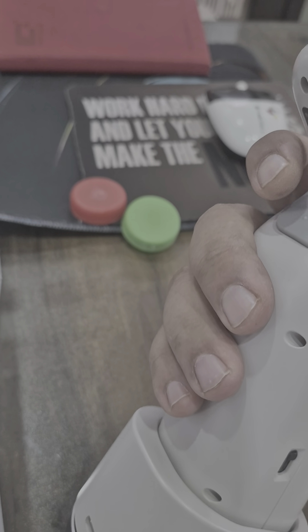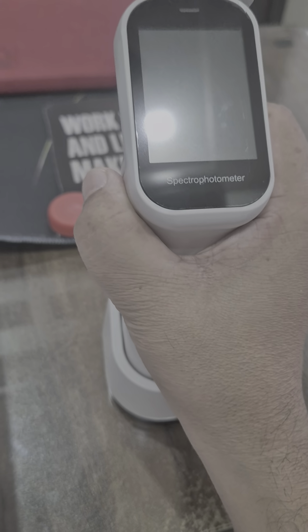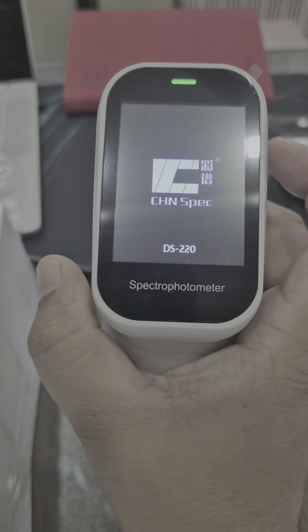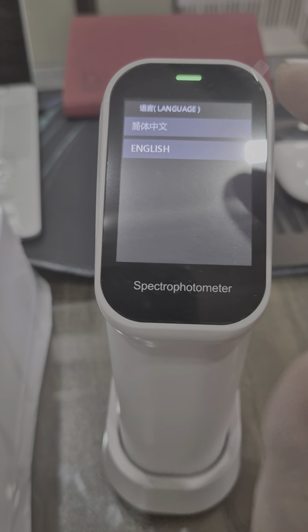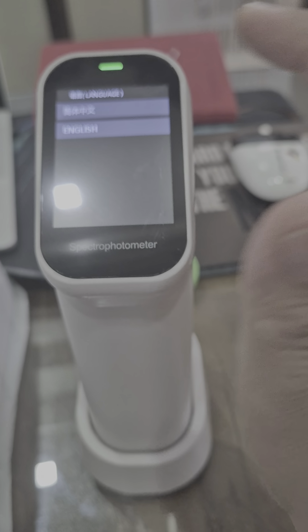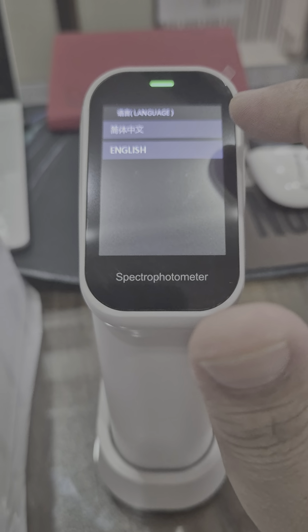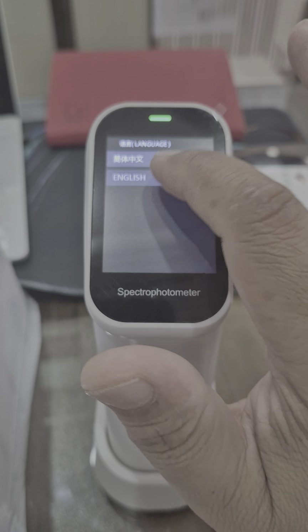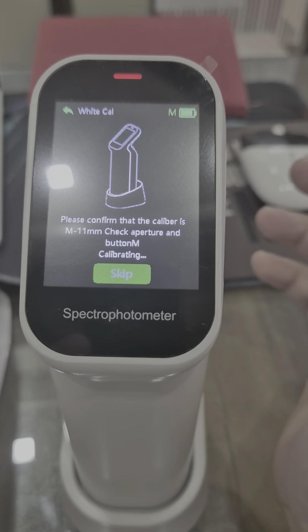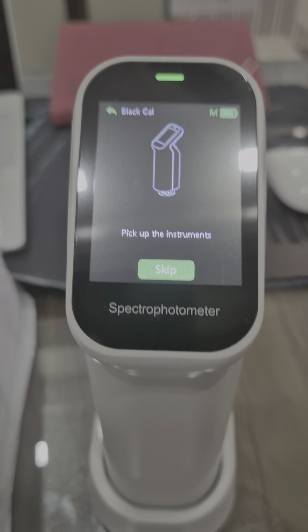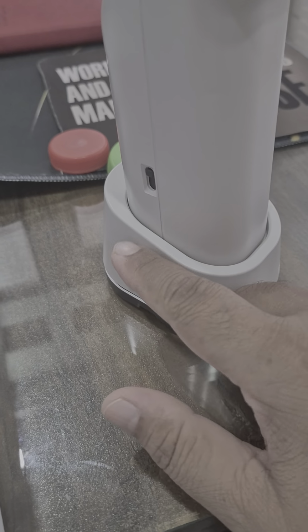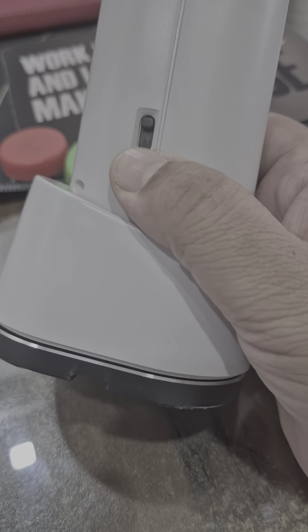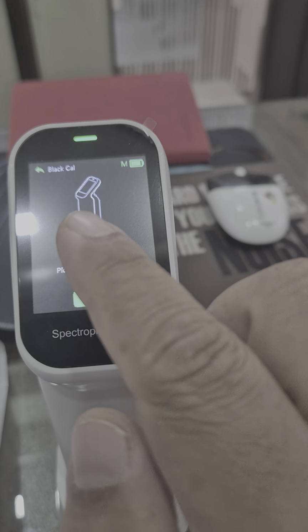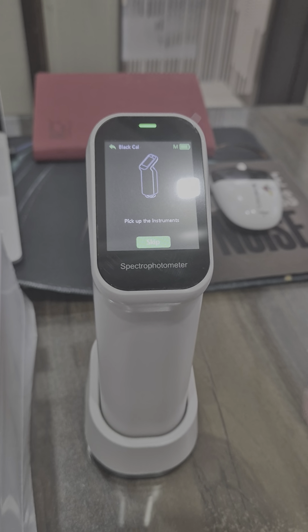We are going to switch this on. This is the back button. We press it on. This is a new instrument, asking for the language selection. We select English. It is asking for the calibration. Automatically it will do the calibration of white. It has the aperture switch M, S, so it is on M. Now it is asking for calibration of black.